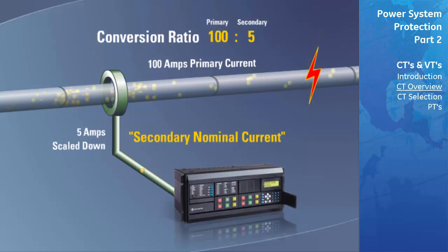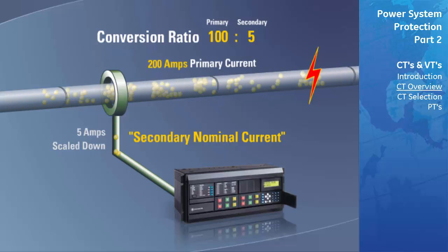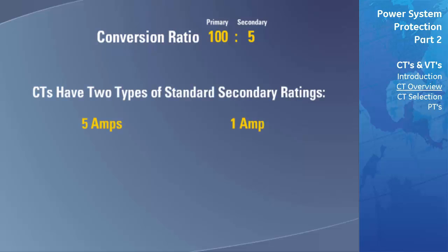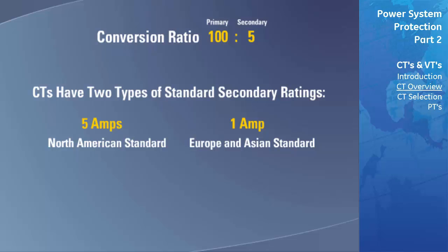If a fault were to occur on this phase that increases the primary current to 200 amps, then 10 amps would be passed to the relay through the secondary windings consistent with the ratio. CTs have two types of secondary ratings: 5 amps and 1 amp respectively. 5 amps is typically the North American standard, while 1 amp is used in Europe and Asia.